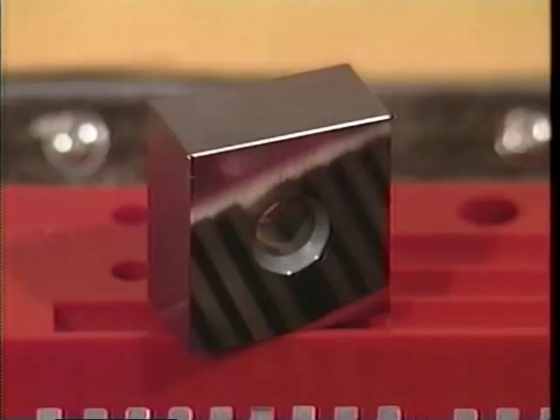Often made of nickel steel or ceramic, gauge blocks are fabricated with attention to terminal surface hardness, microfinish, flatness, and parallelism. These terminal surfaces must be treated with extreme care to avoid scratching and corrosion. After each use, terminal surfaces should be wiped clean with a chamois cloth and lightweight oil.